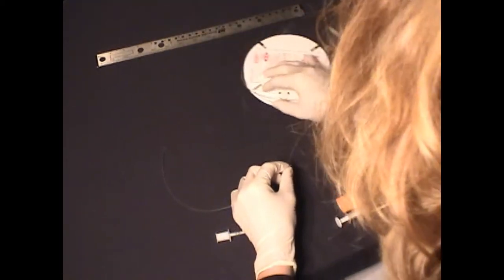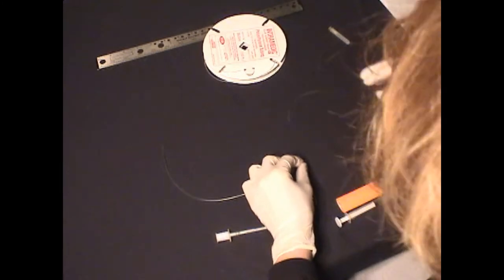You will also want enough non-fenestrated catheter length between the stub adapter and the first fenestration to create adequate room for tunneling the device between the point of entry in the skin and the area where anesthesia is desired. In this example we are cutting tubing to 12 inches total length and our working length will be 4 inches.